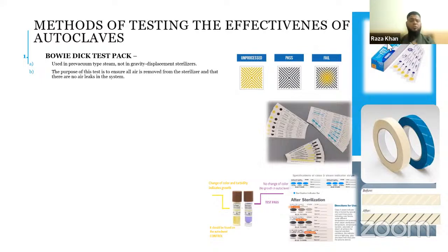One very common test used across the world is the Bowie-Dick test. In this test, we put a chip or paper-type chemical indicator to check whether the air is removed properly from the sterilizer chamber. If there is no air pocket, it ensures that there is no leakage in the chamber. Usually this method is suitable for pre-vacuum type steam sterilizers. It is not suitable for the gravity displacement sterilizer, which is used for glassware sterilization or for unwrapped instruments. The gravity method is also used for decontamination of biohazardous waste.